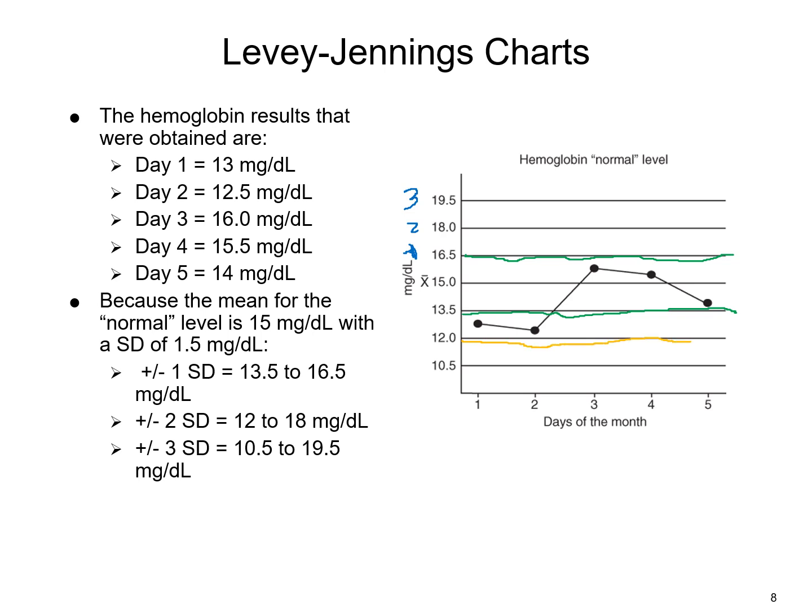So usually once something is kind of in that point, we've got to look a little bit more detail in those rules. And then, of course, if something reaches 3 standard deviations, that's definitely our, whoa, something's wrong. We've got to stop and take a look. So right now, looking at this data, these first 2 here, getting kind of questionable when we're looking at those, as far as, we're going to have to look at those rules a little bit more, but most of the data is within.